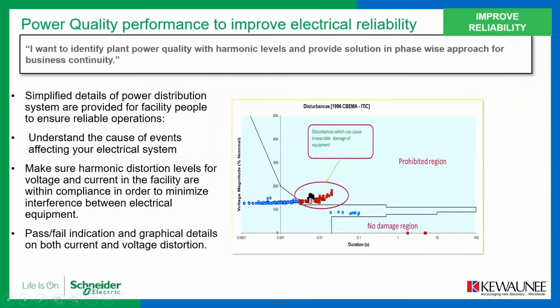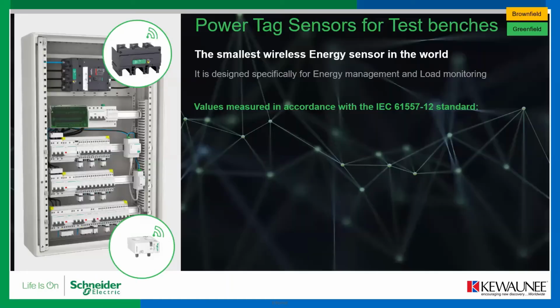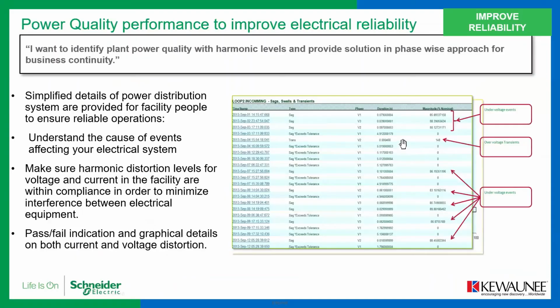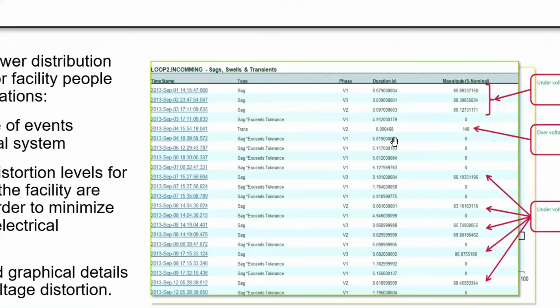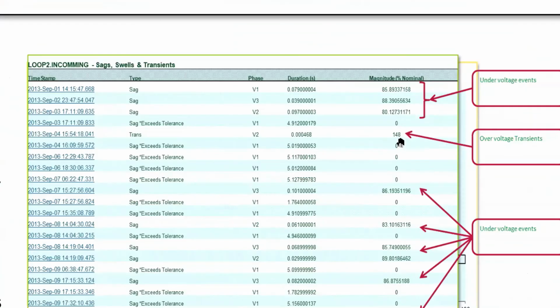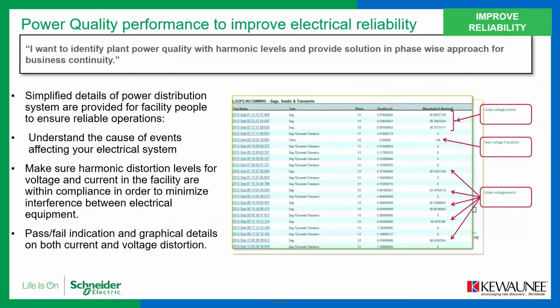For example, if you see in this particular graph, the voltage has exceeded to 148%. That means the typical 415 volts has gone up by 48%, maybe 600 plus volts. It's called an over voltage transient, and it happened in a few microseconds. Similarly, an under voltage happened. It has gone 15% down, from 415 to maybe 350 or 360 volts. You can see the under voltage events here. So we need to know how safe you are in terms of power reliability. If these kinds of events happen frequently, we need to explore some mitigation solution so that we can fix certain issues smoothly.